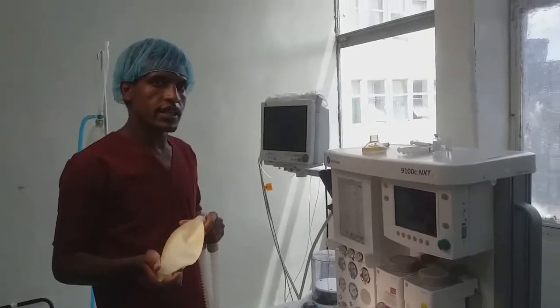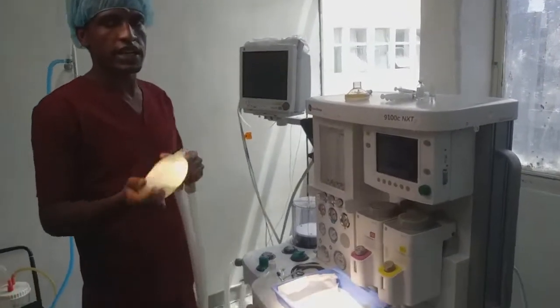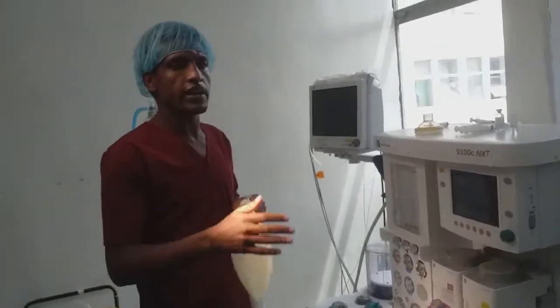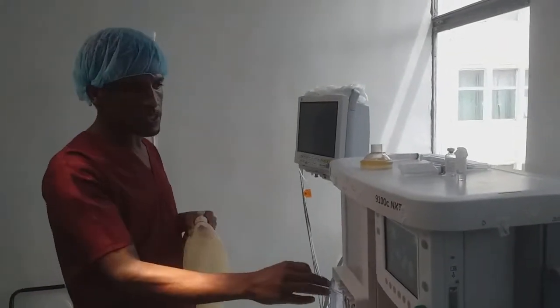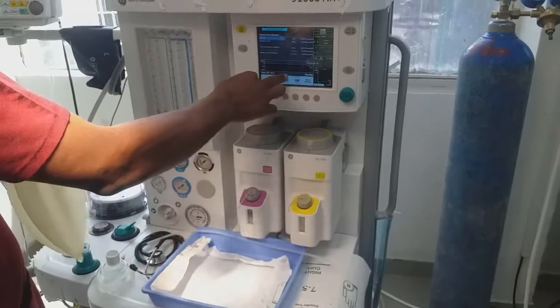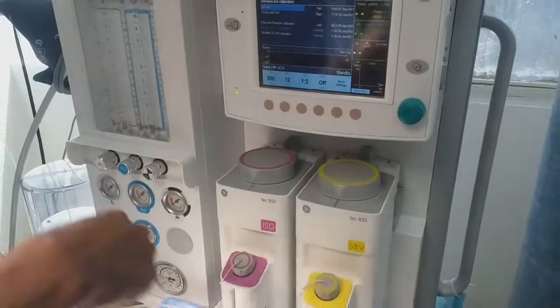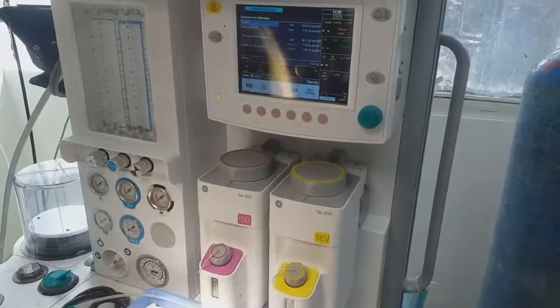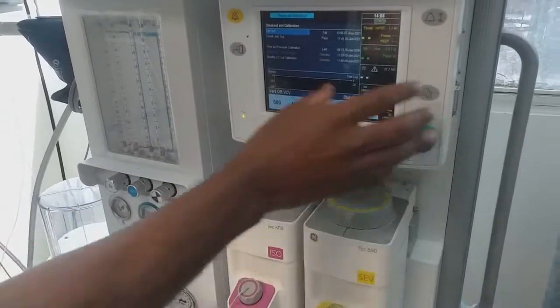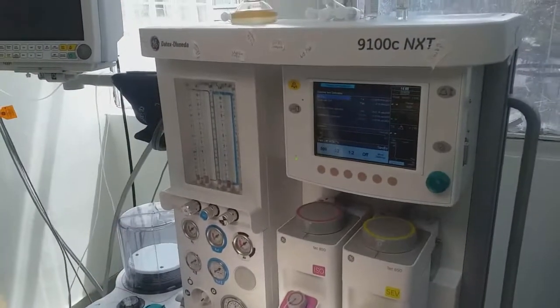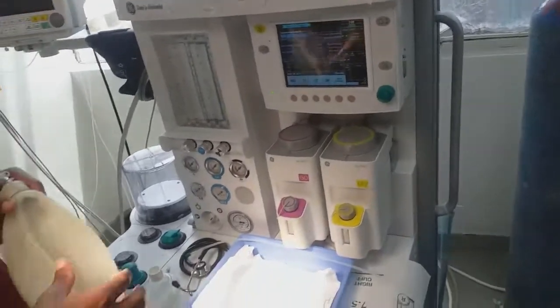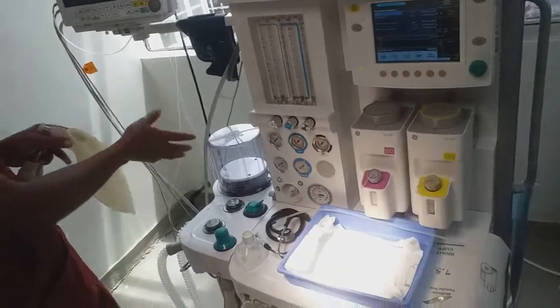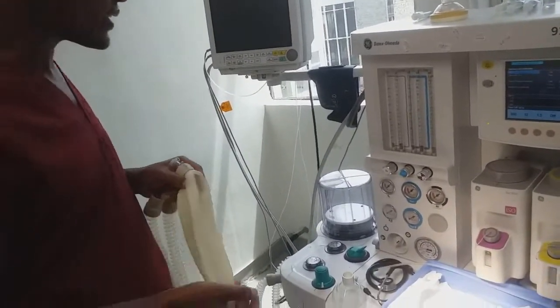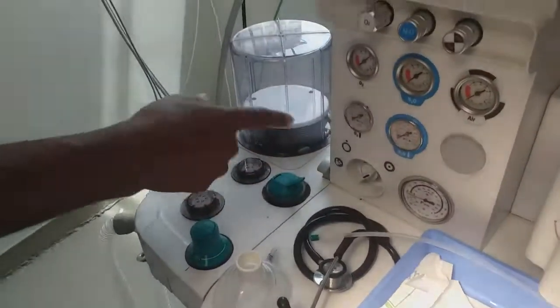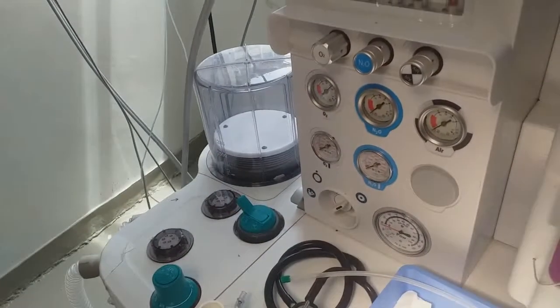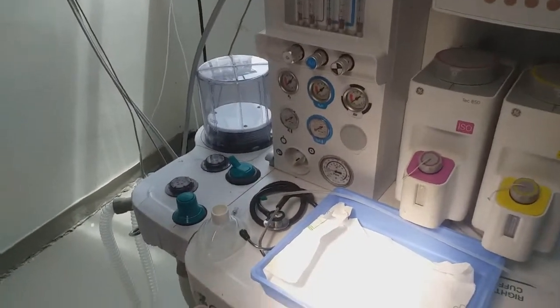Here I am going to check the ventilation system, the manual ventilation system and the mechanical ventilation system. To check the ventilation system, I have to adjust the ventilation parameters first. The ventilation parameters are tidal volume, respiratory rate, inspiratory-expiratory ratio, and the PEEP, or positive end expiratory pressure, which should be adjusted first. These parameters I have already checked, based on the patient I have. After I did this, now I'm going to do the leak test of the lung. To do this, I have to turn the vent bag selector switch to the vent mode. Then with the oxygen flush, I'm going to fill the bellows.